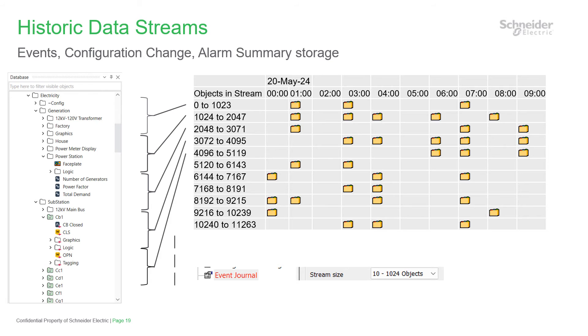To query all database items for an hour, hundreds of files might need to be searched, and to query one database item for a month, large hourly files may need to be searched. So the decision you take here is always going to be a compromise for each history type, but a larger stream size than the default is typically needed. Although the stream size can be changed, doing so after the system has been running live can cause exceptional delays and loss of service, so you really must set this up before going live.